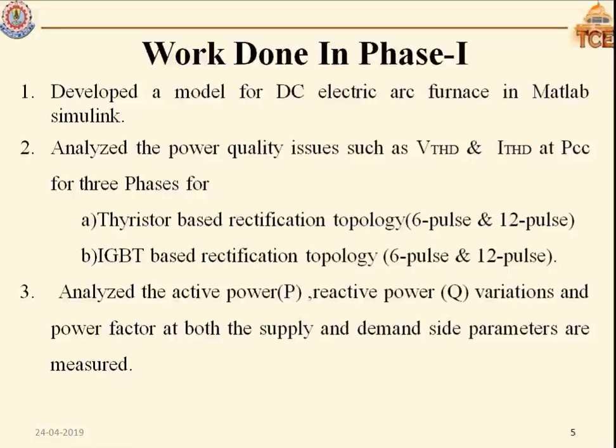For feeding a DC supply to the DC electric arc furnace, we tested two types of topology: the conventional thyristor based rectification topology for both 6 pulse and 12 pulse, and the IGBT based rectification topology for both 6 pulse and 12 pulse. We also analyzed the active power and reactive power variations, and the power factor at both the load side and the supply side, and all the parameters were verified against the power quality standards of IEEE 519-1992.